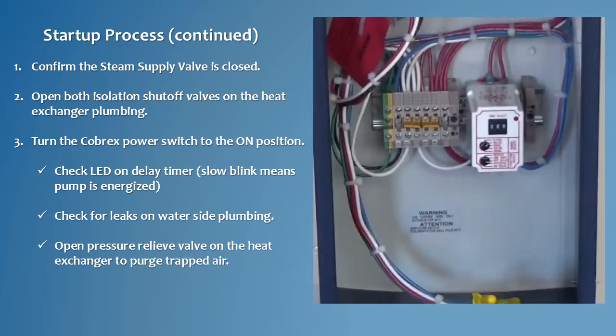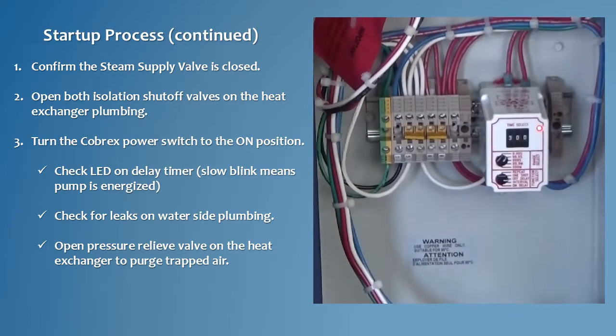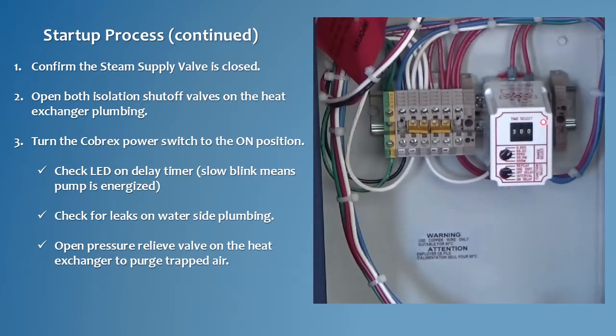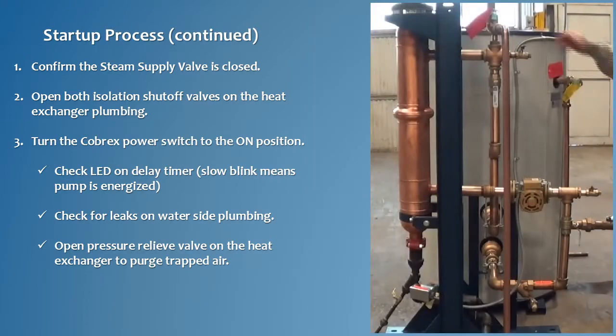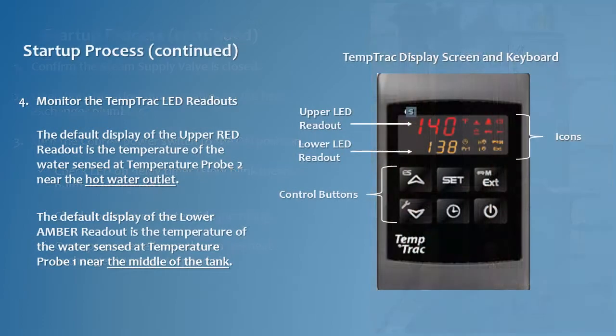The delay timer in the control cabinet will display a slow blinking red LED while the circulating pump is energized. Check for water leaks on the waterside piping. Open the pressure relief valve on the heat exchanger plumbing to purge trapped air. Close the pressure relief valve when a steady flow of water is observed.